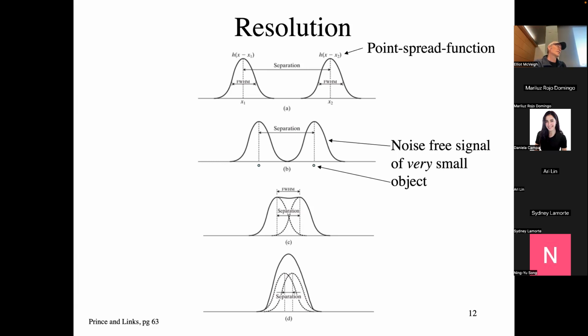So if it's a big spot size versus a small one, do they vary that? They do vary that, but for different reasons. Usually if a person is really big and you need a lot of X-rays to get a shadow, you make the spot size bigger to get more X-rays without burning out your tube. But that spot size will affect the resolution down around the point spread function. So yes.